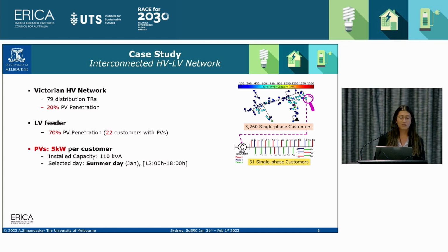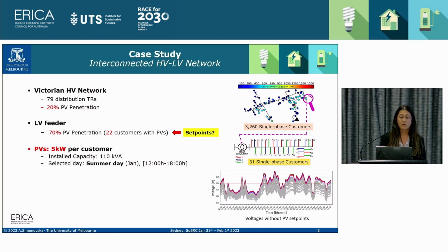Now, with this kind of scenario, with 20% PV penetration for the high voltage network and 70% PV penetration for the low voltage feeder, we have voltage rise issues as shown in the figure on the bottom. Therefore, we need to calculate the set points. This is for a summer day, in January, and you can see that from midday, 12 p.m., until 6 p.m., the voltage rise issues are really significant. And the installed capacity is 5 kilowatts per customer.